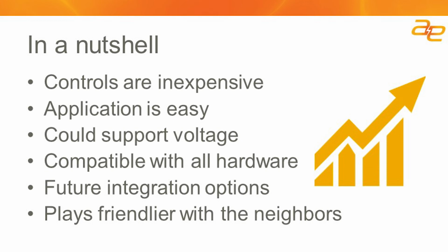And we have a utility that we're working with now on defining how they would send us a power factor signal from their substation, and we would adjust the plant's power factor output to help them minimize the penalties they pay when they're buying power outside of the standard power factor range that they're supposed to be operating in.